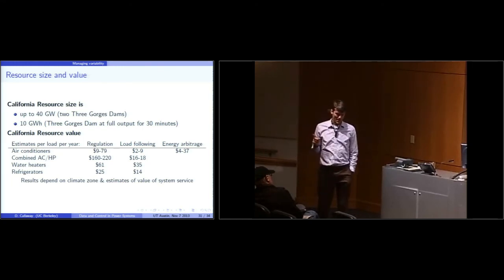One thing that I will say, though, is that maybe you're familiar with the work that they've done at Pacific Northwest National Labs. Yuri Makarov has been involved in this, where they've said, let's take a look at the signals that generators are getting for AGC, 4-second signals, and compare that to what they're actually doing. And there's roughly a 1 to 2 minute lag between what they're being told to do and what they're actually doing.